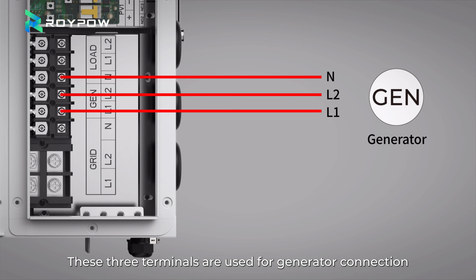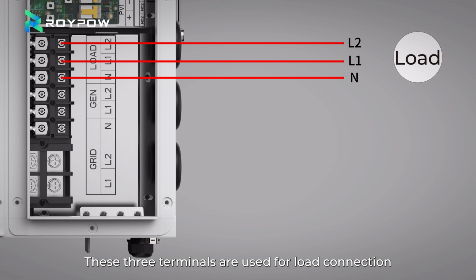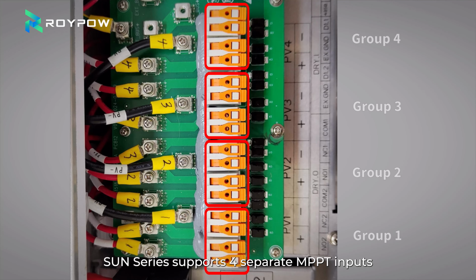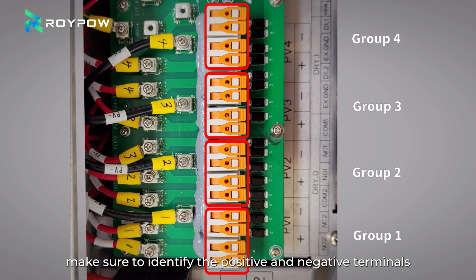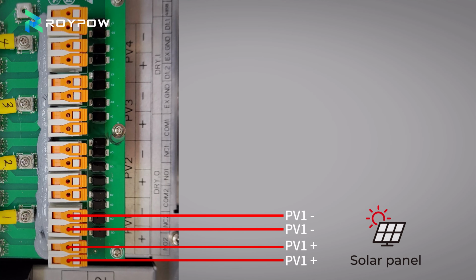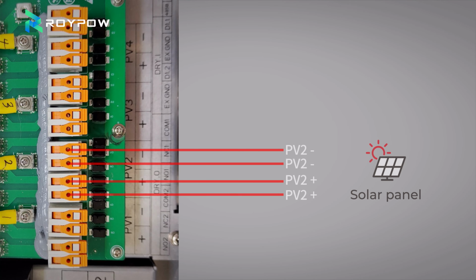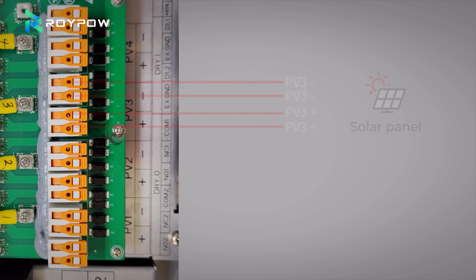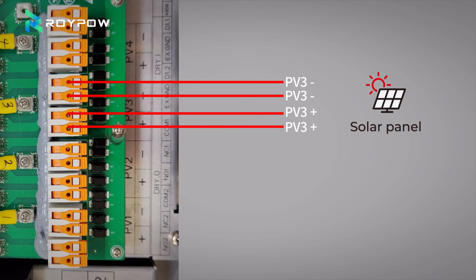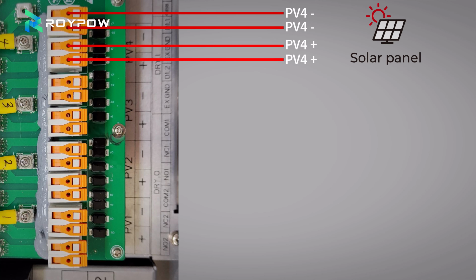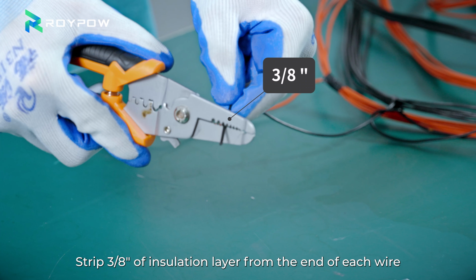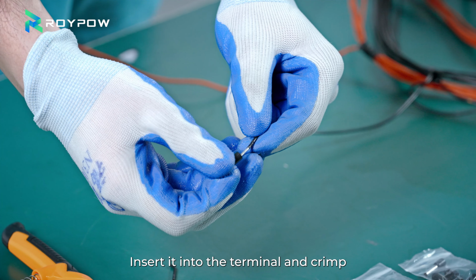These 3 terminals are used for generator connection. These 3 terminals are used for load connection. Sun series supports 4 separate MPPT inputs. When connecting the wires, make sure to identify the positive and negative terminals. Strip 3/8 inch of insulation layer from the end of each wire. Insert it into the terminal and crimp.